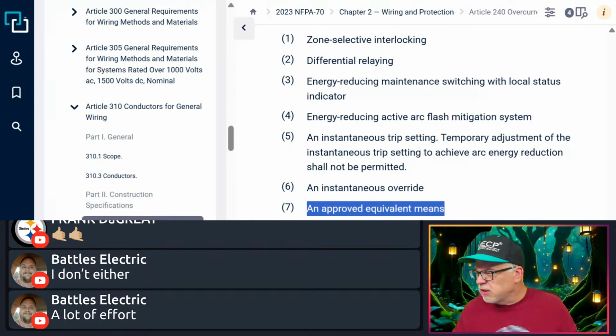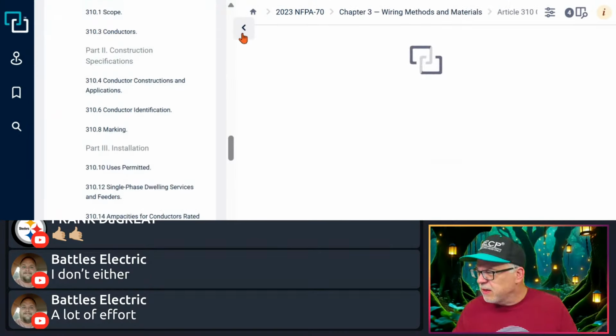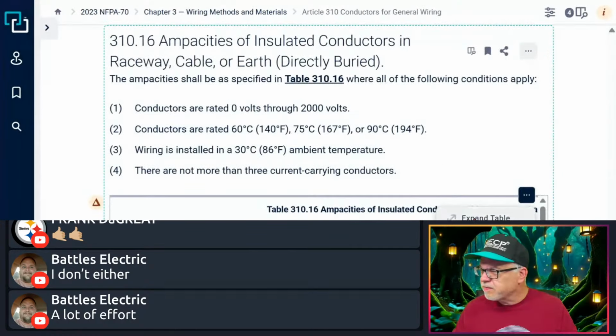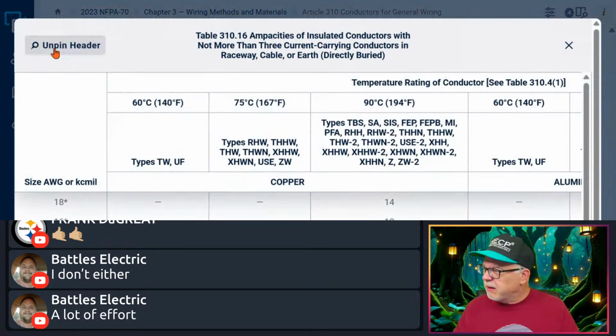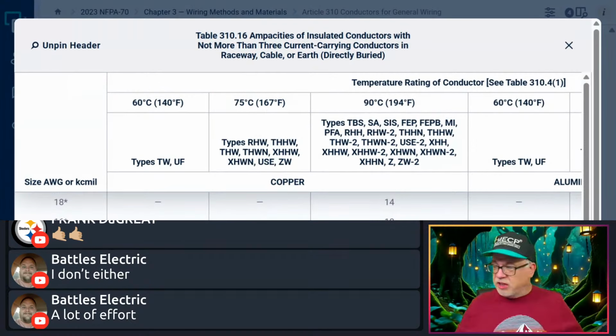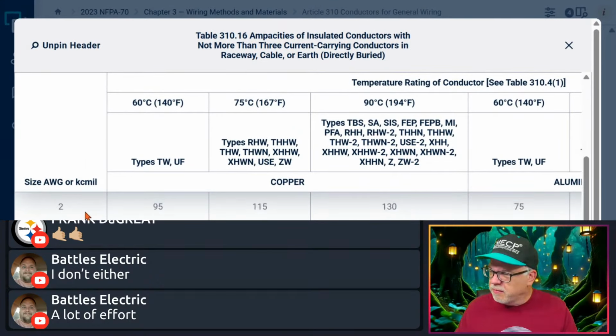All right, so I'm going to look here at the ampacity of a conductor, and I'm going to pop this out for you. I'm going to pin it. Okay, it's telling me everything's 75. So I'm going to come down and see, okay, a 12 gauge is good for 25 amps. So remember what it said? It said, well, Paul, minimum circuit ampacity is 23. Maximum overcurrent protection is 40. You're saying, okay, well, the minimum size I can run is a 12. So there's the 25 amps right there under the 75.